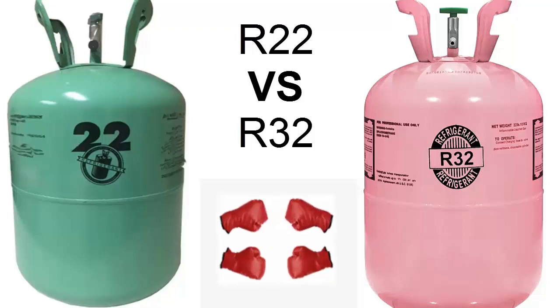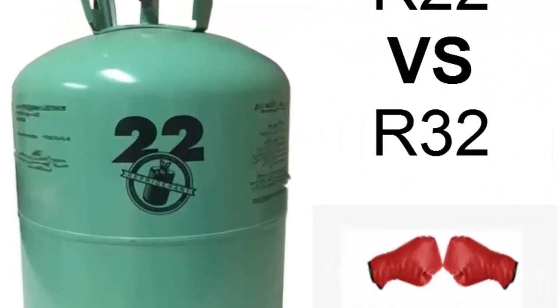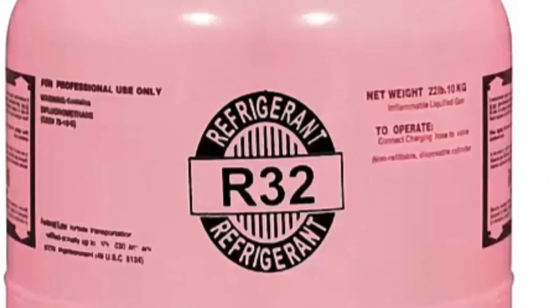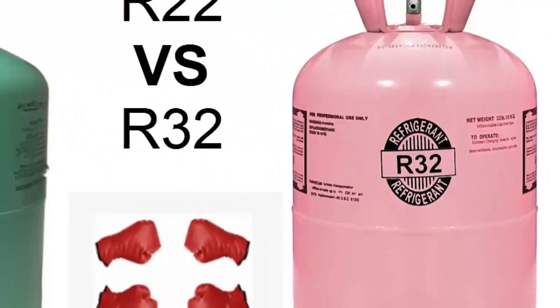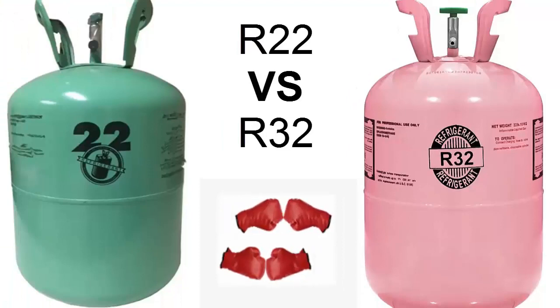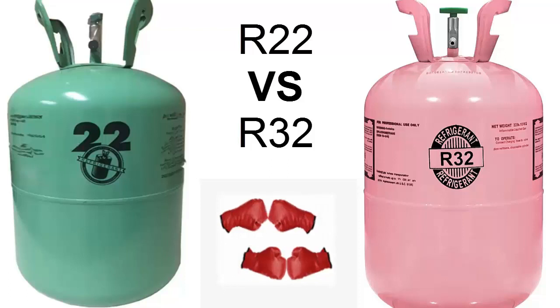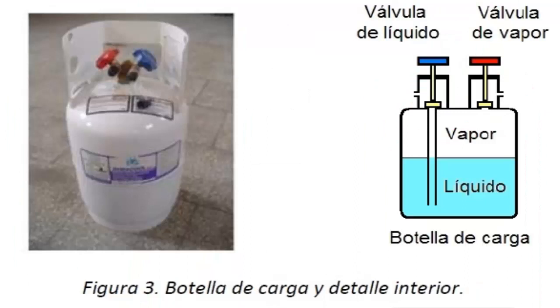In today's video, we are going to develop a comparison between two refrigerant gases. We're talking about R22 and R32 refrigerant. Let's start by saying that both R22 and R32 are internally composed of a single component, with no internal presence of gas mixtures, allowing both to be loaded in both liquid and gaseous phases.